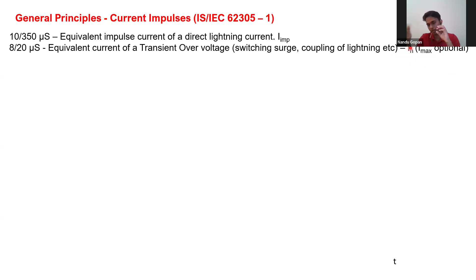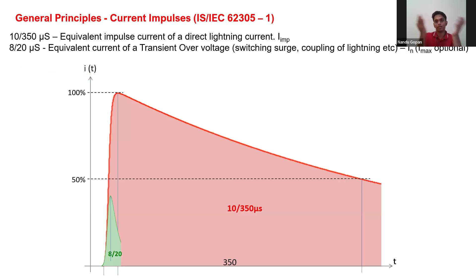So if you're asking me what 10 by 350 and 8 by 20 are, 10 by 350 means it reaches 100% of the current intensity in 10 microseconds. So if it is a 100 kiloamp strike, it reaches 100 kiloamps in 10 microseconds and 50 kiloamps in 350 microseconds. Same thing for 8 by 20, it reaches 100 kiloamps at 8 microseconds and 50 kiloamps in 20 microseconds. That is what 10 by 350 and 8 by 20 mean. So 10 by 350 will be a much larger impact because of the longer time; the energy will be much larger compared to 8 by 20 with the same current parameters.